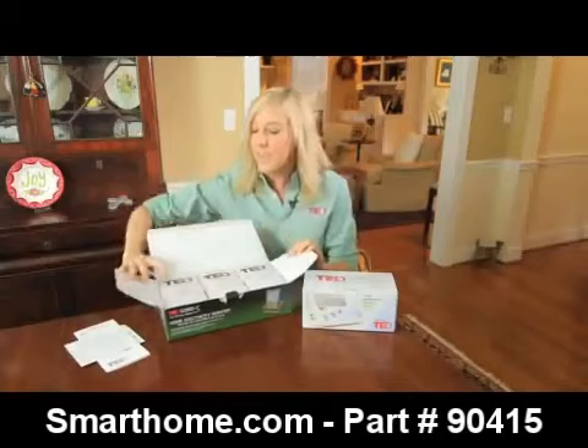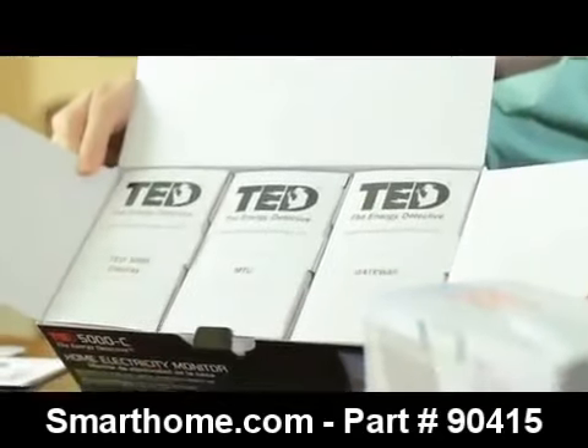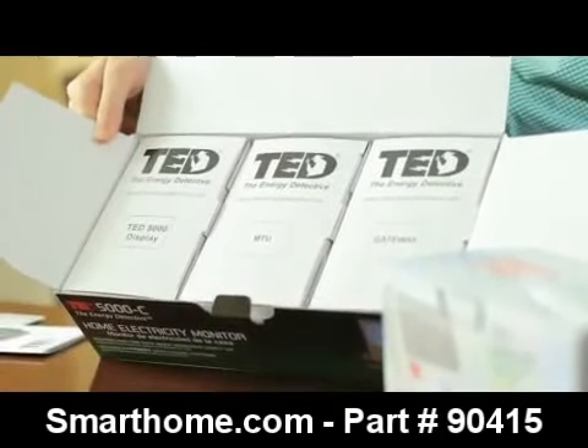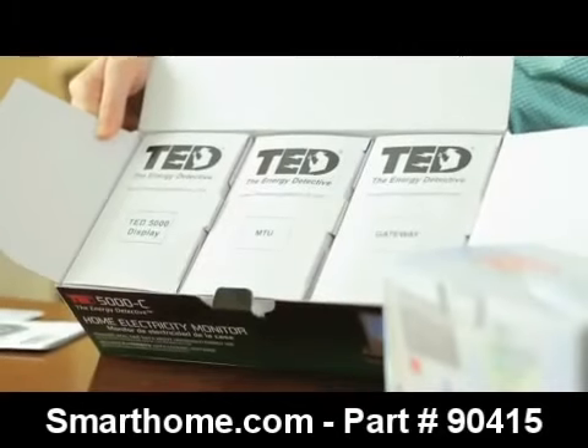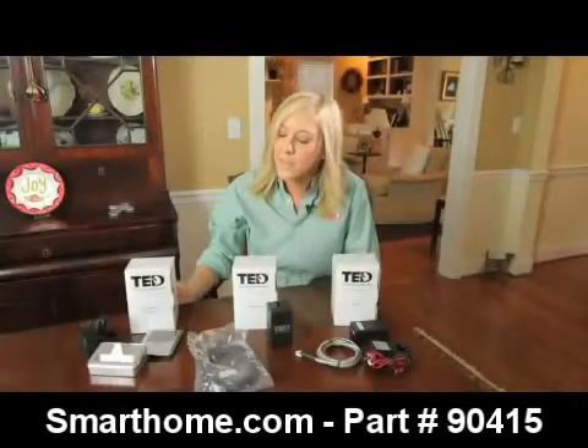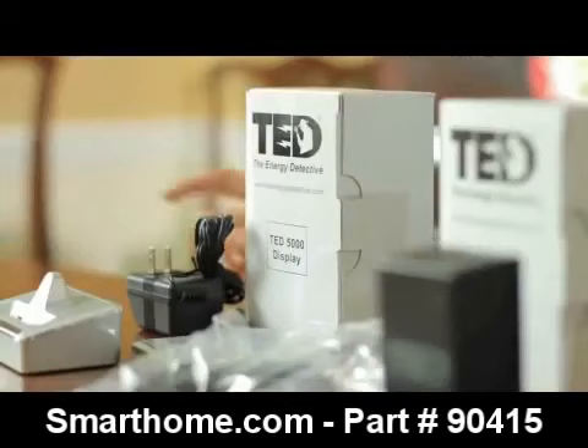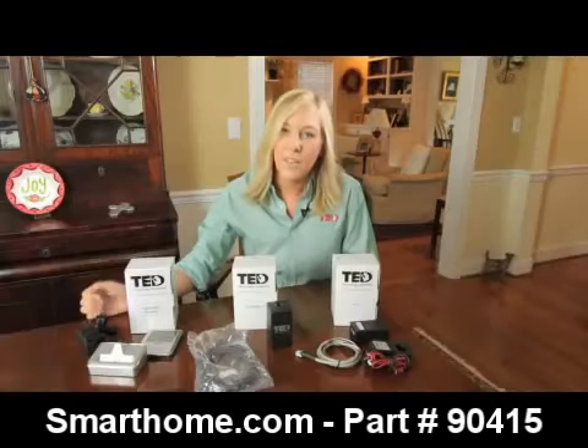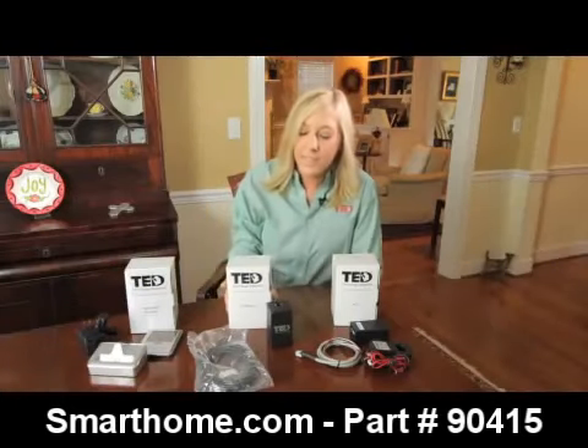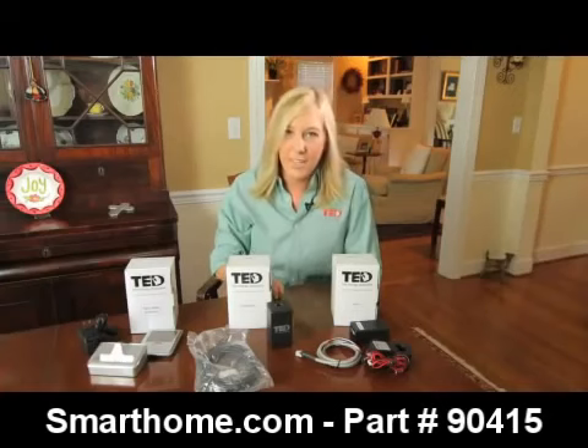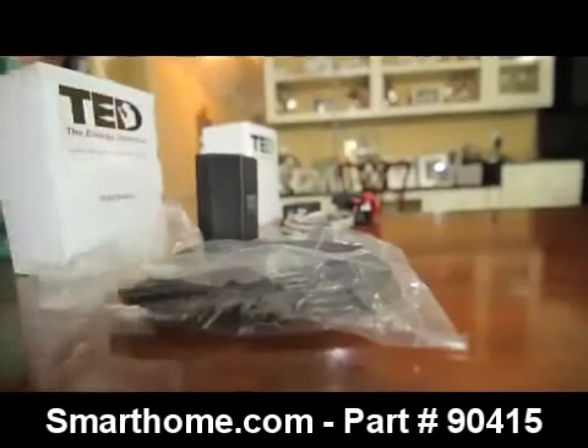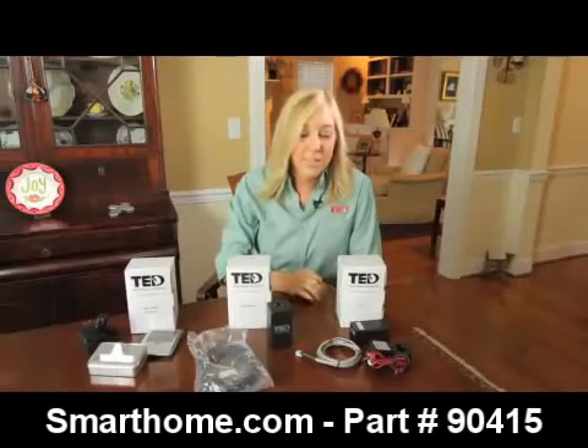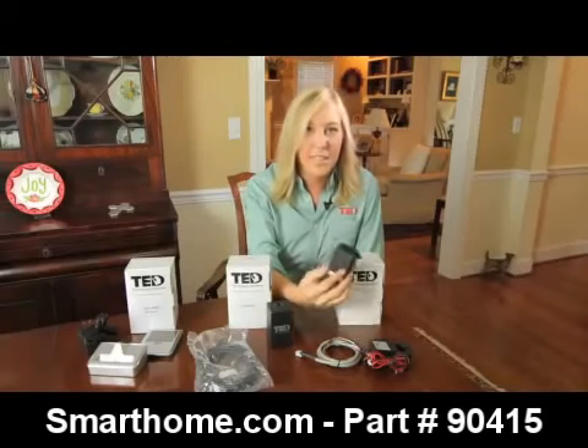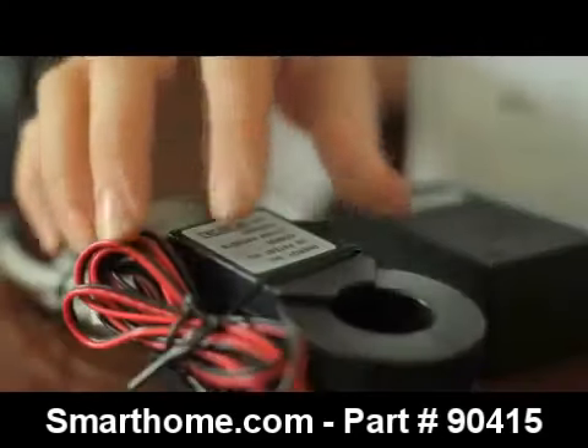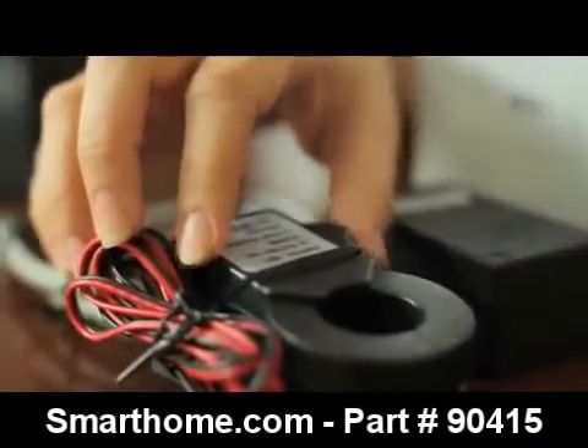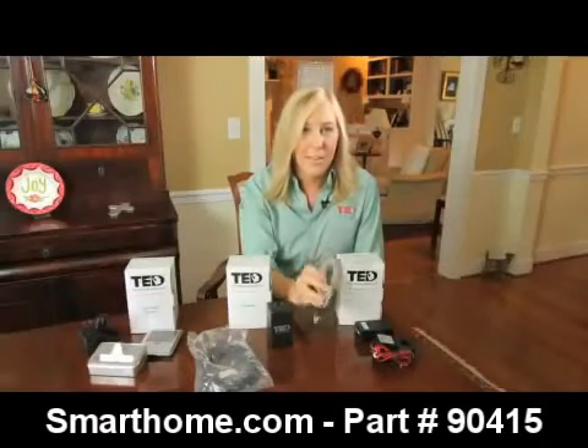In addition, there should be three main component boxes: a TED 5000 display, an MTU and CT box, and a gateway box. In the TED 5000 display box, you'll find one power supply, one charging stand, and one optional wireless display. In the gateway box, you'll find one gateway and one Ethernet cable. And in the MTU box, you'll find one measuring transmitting unit, also known as an MTU, one pair of current transformers, also known as CTs, and one power cable.